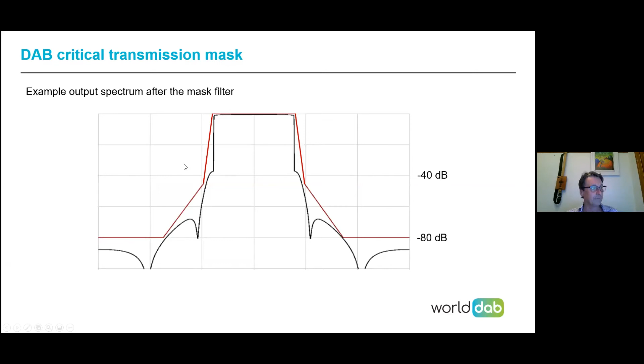Just remember, you don't get filtering for free. It does take some power, even with cavity filters. These are mechanical filters. You can see all the adjustments on the right-hand side here. It can be quite a complex operation to get a very good filter specification, or combiner specification in this case. And a typical loss through one of these systems is about 1 to 1.5 dB. Here's a Spinner, their systems 1 to 1.3 dB at the center frequency.